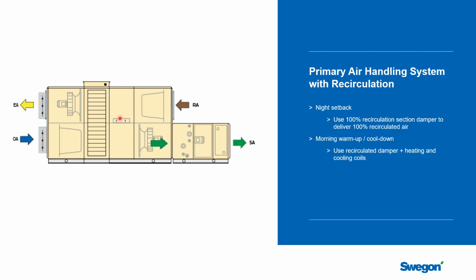So if you have a recirculating section, you can do something like this, where during night setback, you leave the outside air dampers closed, you leave the exhaust air fan off, and then you just recirculate air through the unit. You normally would not heat or cool it.